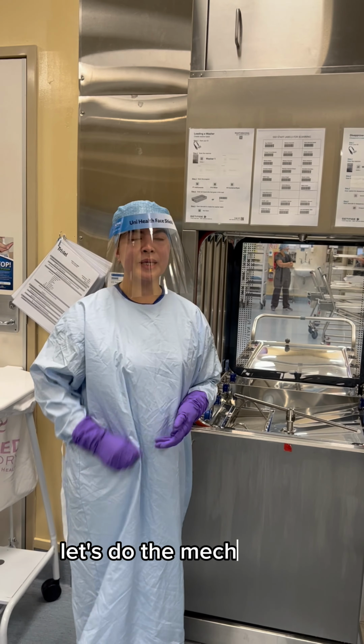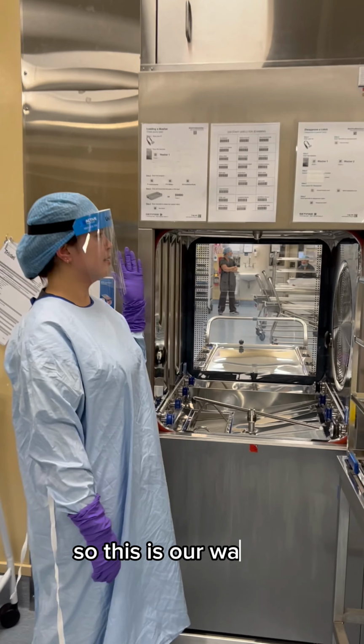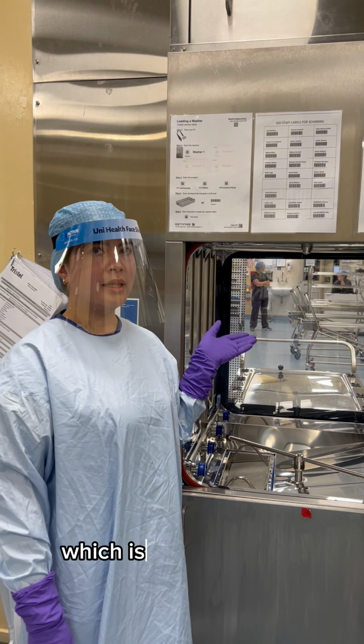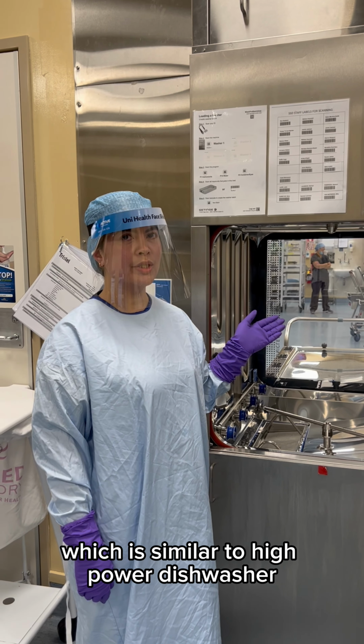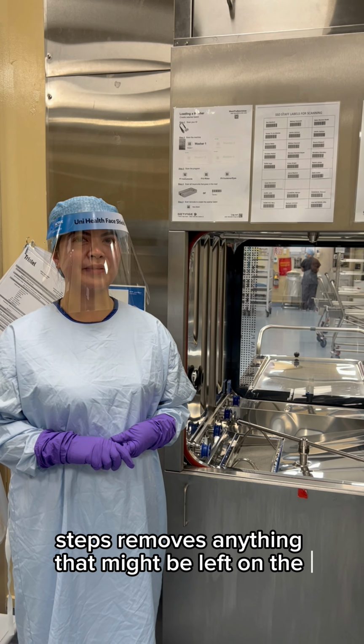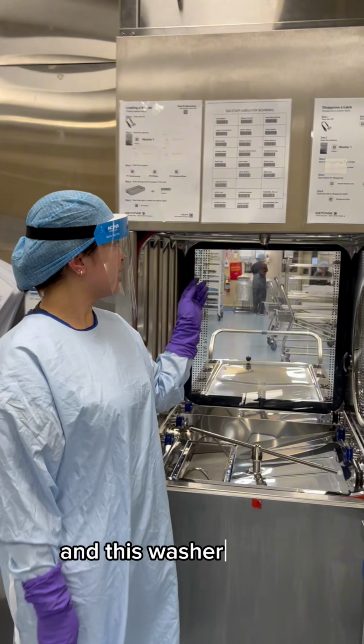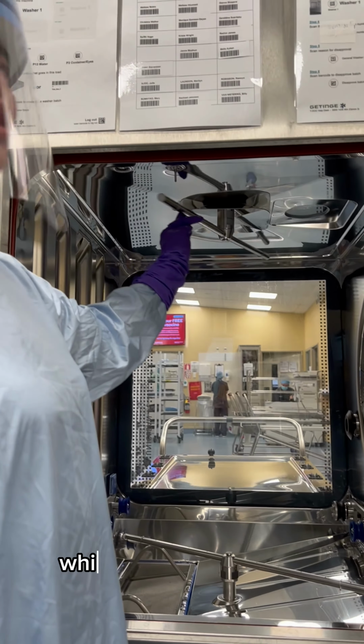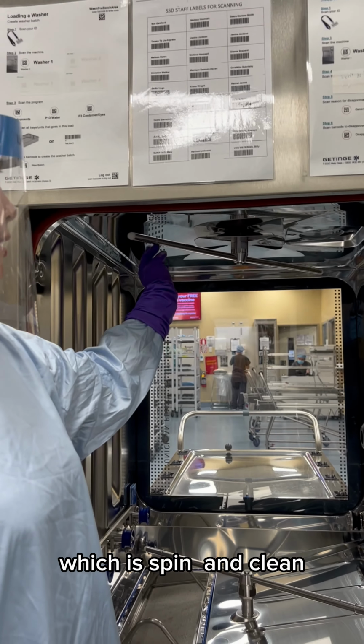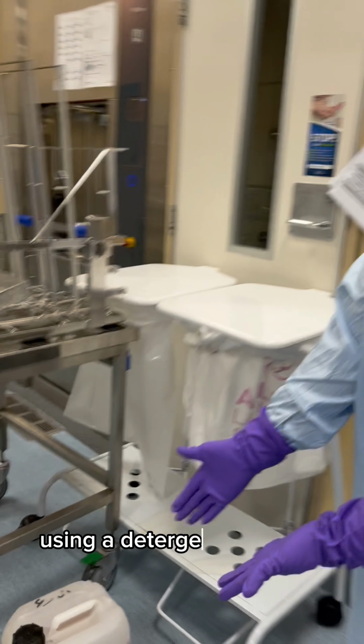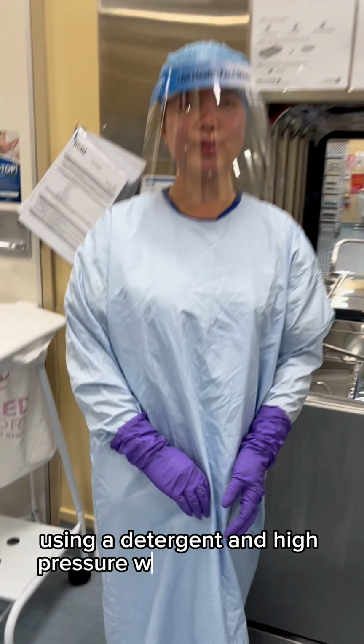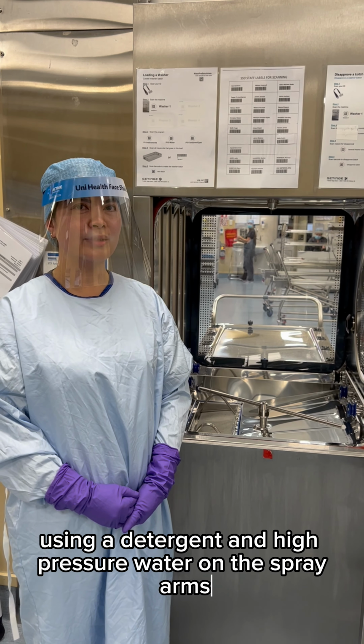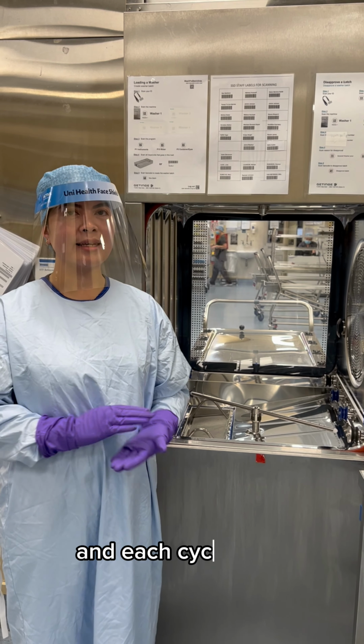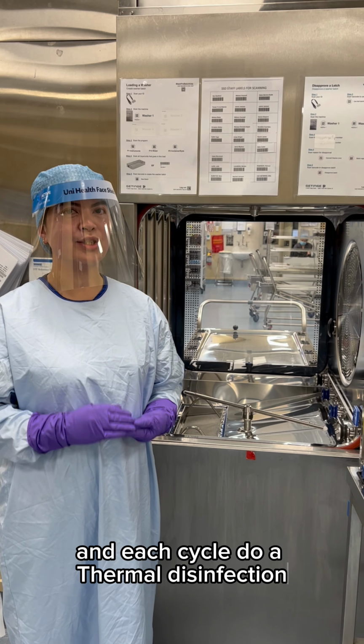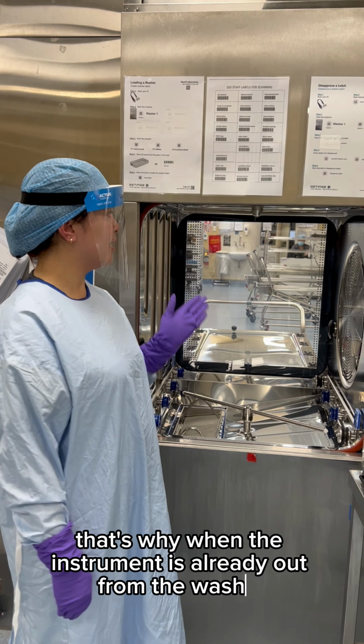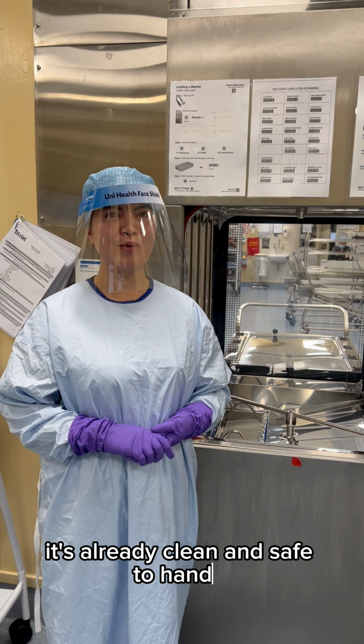Now let's do the mechanical cleaning. This is our washer disinfector, which is similar to a high-powered dishwasher. This step removes anything that might be left on the instrument. The washer has spray arms which spin and clean using detergent and high pressure water, and each cycle does a thermal disinfection. That's why when the instrument comes out from the washer, it's already clean and safe to handle.